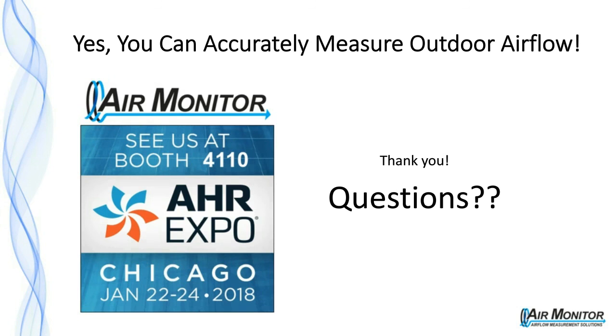In other words, there's some type of inlet device that does not have either published pressure drop information or doesn't match the calibration curve. If the meter is calibrated against a factory standard, which is the recommended way to go, we definitely recommend a field validation. In other words, use the measurements that you see in the field from the instrument as the basis for comparing, but we don't recommend recalibrating a factory calibrated device, because the field devices won't generally be as accurate. It really only comes into play if something was not able to be fully characterized at the factory. So that is a great question, something that we deal with quite a bit.